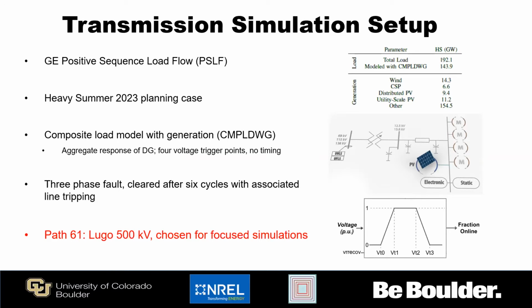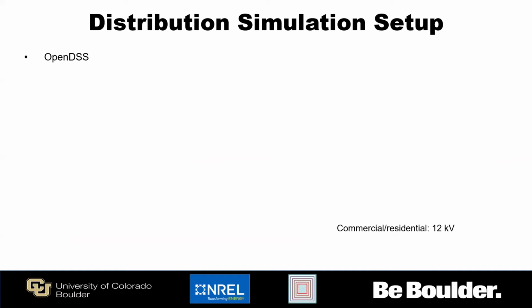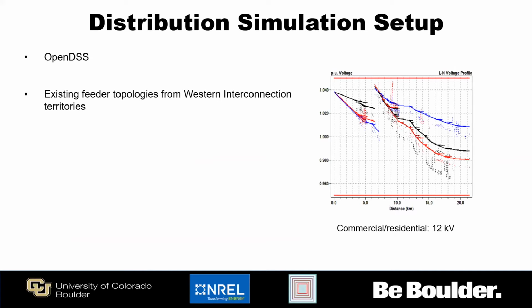What we are looking at in terms of fault is a three-phase fault on path 61, so that's the Lugo bus, at the 500 kV level. This was chosen because this is one of the more critical paths in the Western interconnection. We take that information from the transmission side and pass it down to the distribution side, and we utilize OpenDSS here using existing feeder topologies that we've collected from utilities in the Western United States.